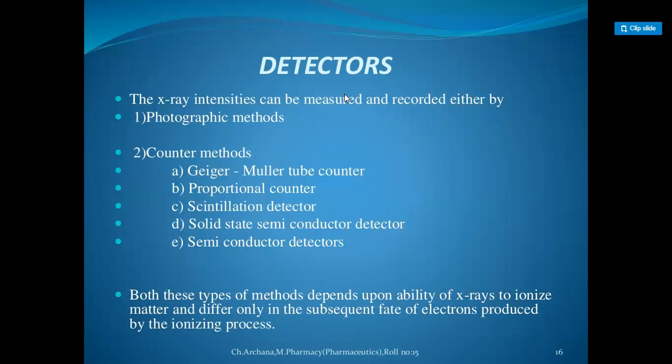X-ray intensities can be measured and recorded either by photographic methods or counter methods. Counter methods include the Geiger-Müller tube counter, proportional counter, scintillation detector, and solid-state semiconductor detector. Both types of methods depend on the ability of X-rays to ionize matter and differ only in the subsequent fate of electrons produced by the ionizing process.